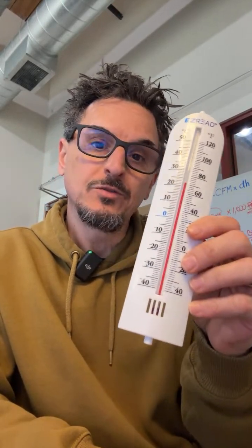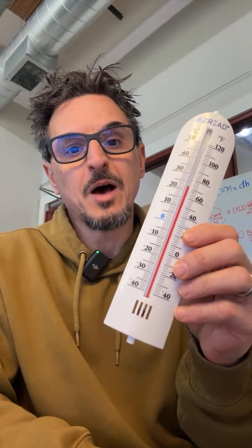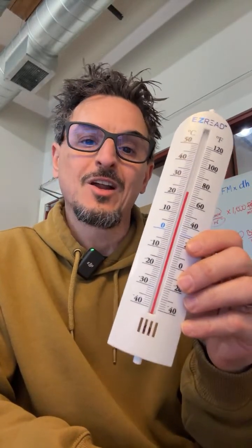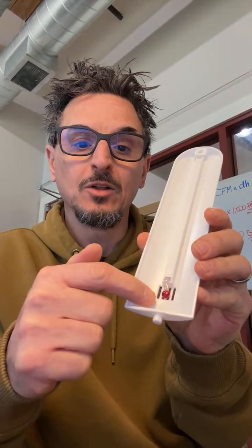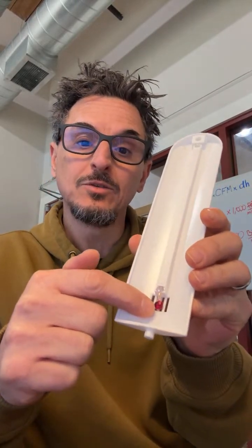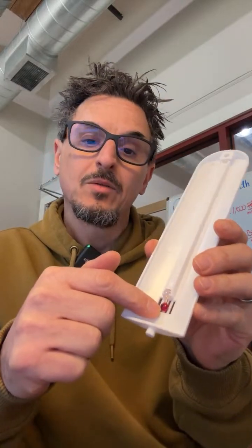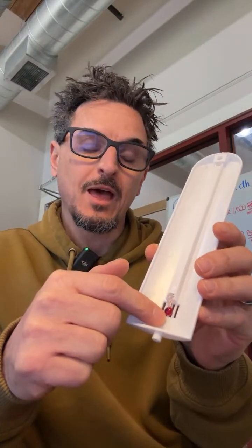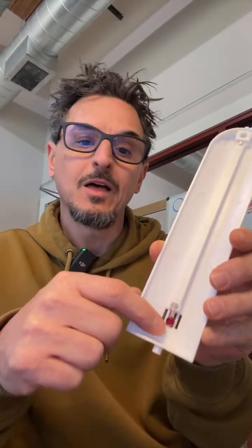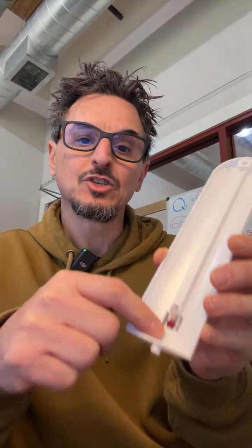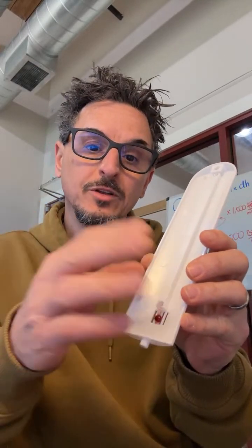So wet bulb is used as an indicator of the amount of moisture that's in the air. And how we get the term wet bulb is, what you do is you take a thermometer like this, and you add what's called a wet wick or a wet sock to the bulb. Now, what happens is the water in that wick or sock will evaporate depending on the amount of moisture that's in the air. So if you had a wet sock on this bulb and the air was extremely dry, a lot of moisture would evaporate.